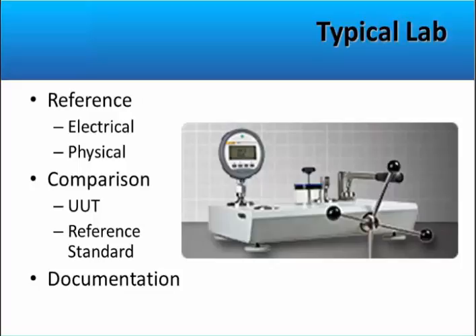They usually compare the unit under test to a very closely guarded and defined reference standard, and they are able to produce the documentation that is often required for checking of the various systems, including when it was last checked, the conditions under which it was verified, the results of the verification, and also traceability of the standard back to its own standard. Just as an instrument out in the field has to be checked against a standard, the standard itself also has to be checked against a higher accuracy standard, and that could be through a national standard or an international standard, but there needs to be that traceability.